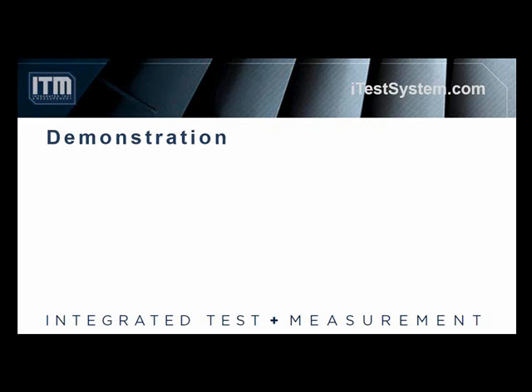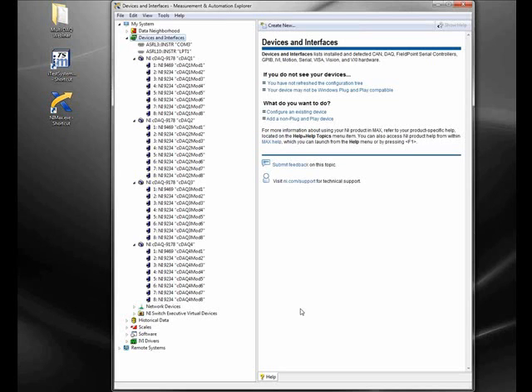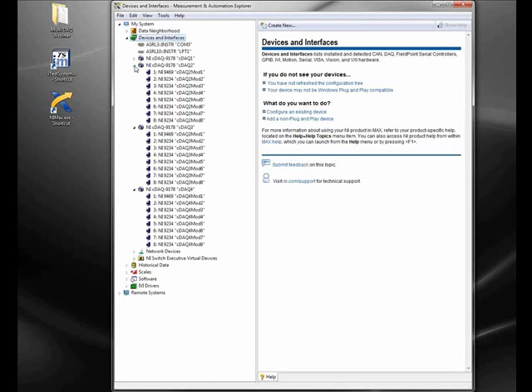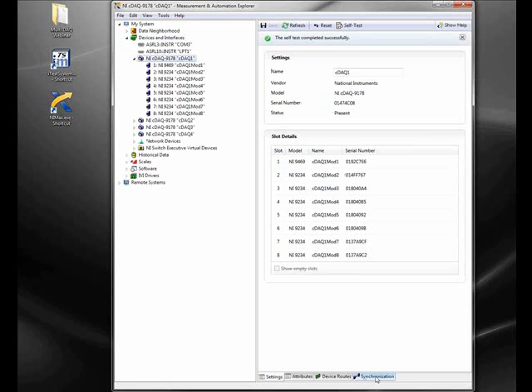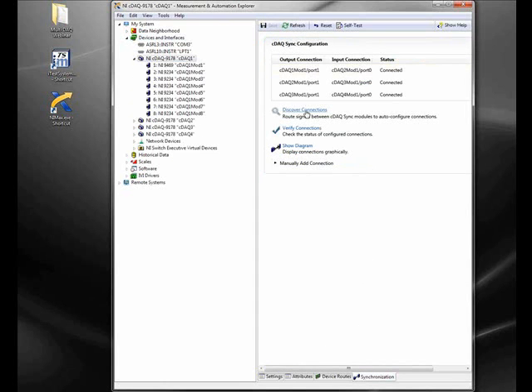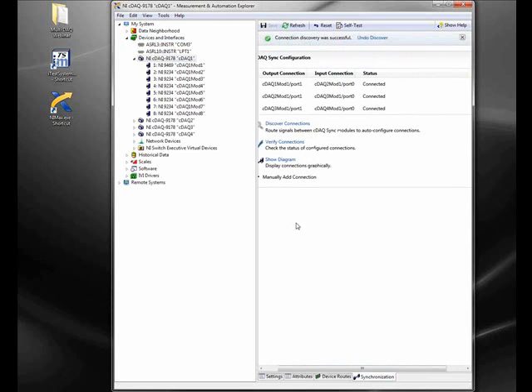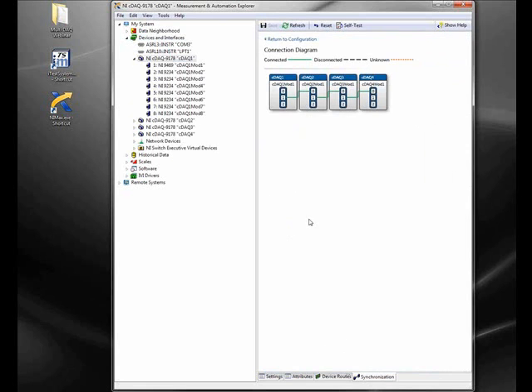Now we're going to jump to the part of the presentation where Todd actually shows the software in action. The first thing I'm going to do is bring up the Measurement Automation Explorer software. As you can see, we have four cDAQ chassis connected to this computer right now. The main thing I wanted to show you is the 9469 sync module connected. I'll show you how we check the synchronization of our system — basically, we'll click Discover to verify connections. It is connected and synced. You can show a diagram of the actual setup; green lines indicate a good connection and synced system, orange dotted lines mean they may be connected incorrectly, and black dashed lines indicate things are completely disconnected. Right now we have a system that is synced and communicating correctly.